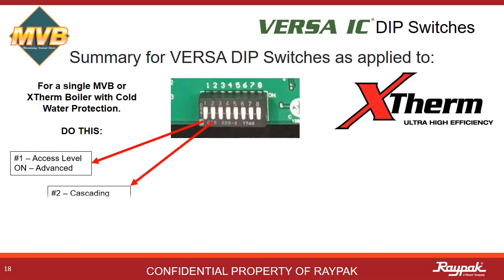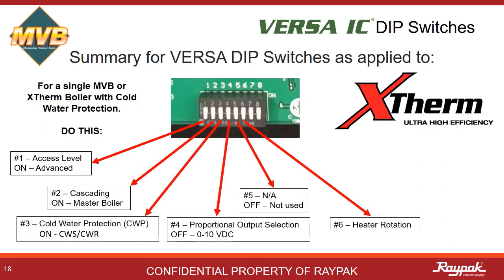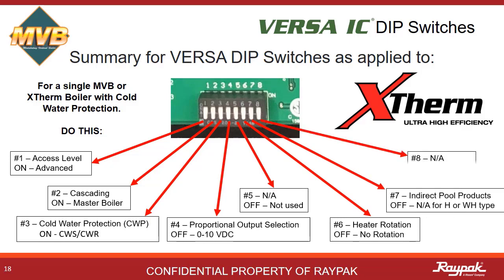If you are setting up a single MVB or Xtherm boiler with a cold water protection system, set Versa Dipswitch numbers one, two, and three on, with all others off. Be careful when adjusting the Dipswitches — that soft plastic tab can shear off easily. Use the tip of a ballpoint pen, or better yet, a Dipswitch tool. If you are using a screwdriver, you might shear off that little tab.